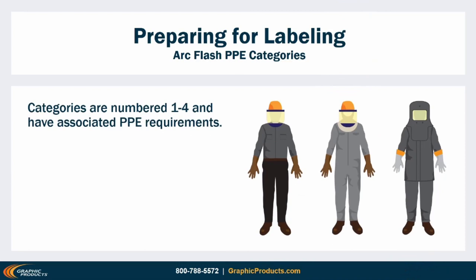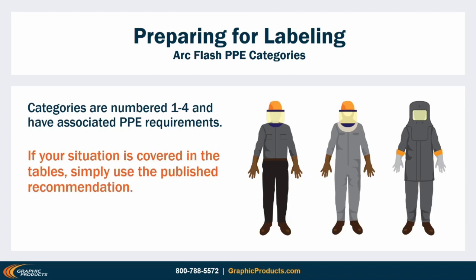The other approach is a shortcut. Instead of doing a lot of math, you can simply read a set of tables that NFPA has prepared in Article 130.7 C 15. These tables assign broad categories numbered 1 to 4 to some recognizable situations, and each category corresponds to a standardized list of PPE items and ratings. If your equipment and installation are covered in those tables, all you need to do is find the applicable entry and use the published recommendations. However, the tables don't cover all possible situations, and if your installation isn't covered, then there's no way to meaningfully apply the category system — the shortcut isn't available and you'll need to do an analysis.